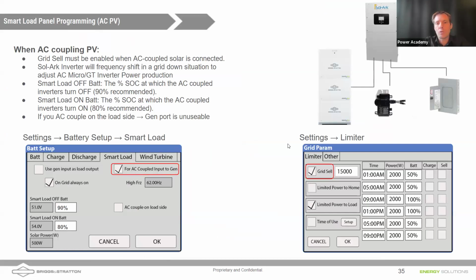So if the grid's on, keep that solar alive, right? You do have to enable grid sell if you're going to use AC, you're going to allow AC coupled solar. So you have to have that grid sell box checked. And now notice that the percentage values here have switched. Why is that, Daniel? Why do we want to have the battery shut off at a high percentage like 90%? Well, we don't want to overcharge the battery using our AC coupled solar.